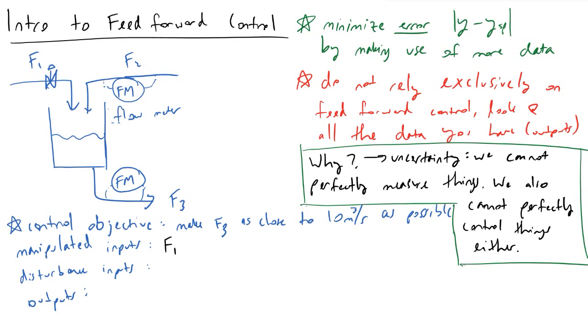We look at what our disturbance inputs are, and F2 would be a disturbance input because someone upstream is producing however many cubic meters per second of flow rate, but we need to make sure the mixed stream hits our target. The output in our process is F3. So if you were designing a feedforward controller for this process, you would look at whatever stream F2 is, subtract it from your setpoint, and determine what flow rate you need to make F1.